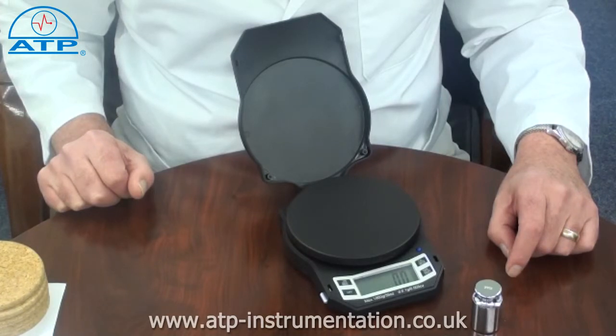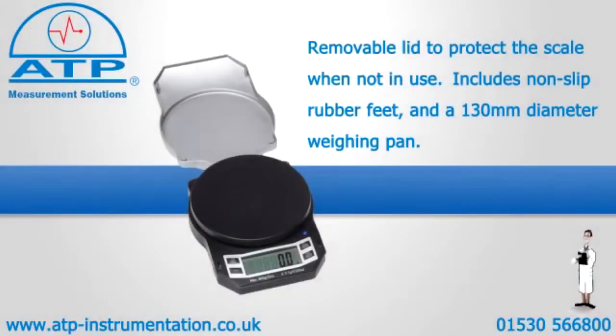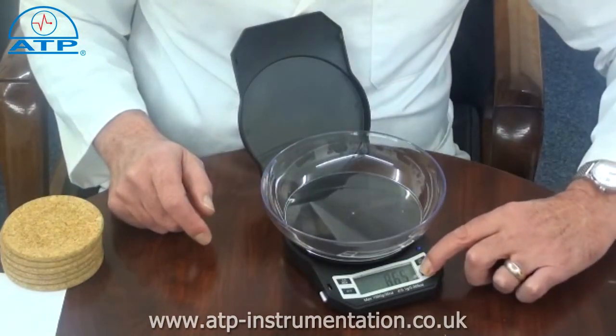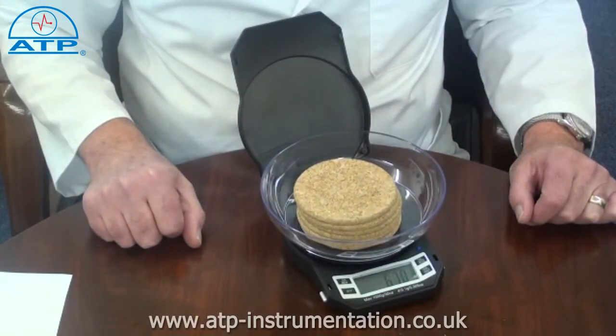There is a simple calibration program to ensure accurate weighing. The tare facility allows a container to be placed onto the platform. Press tare and the value will be zero. By then adding contents to the container, the displayed value is the contents weight only.